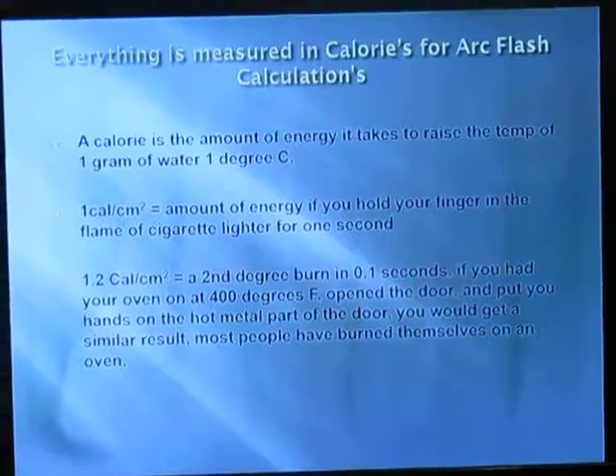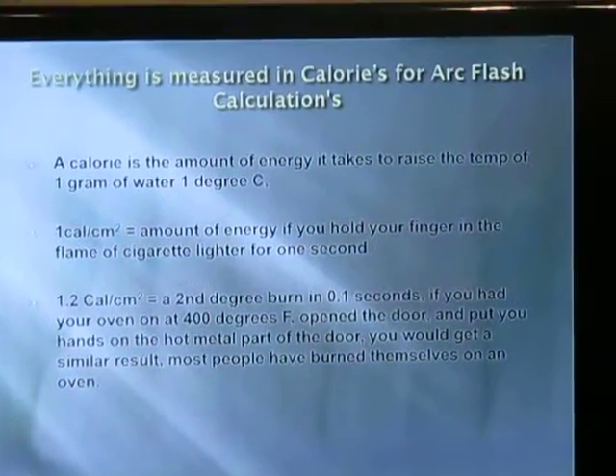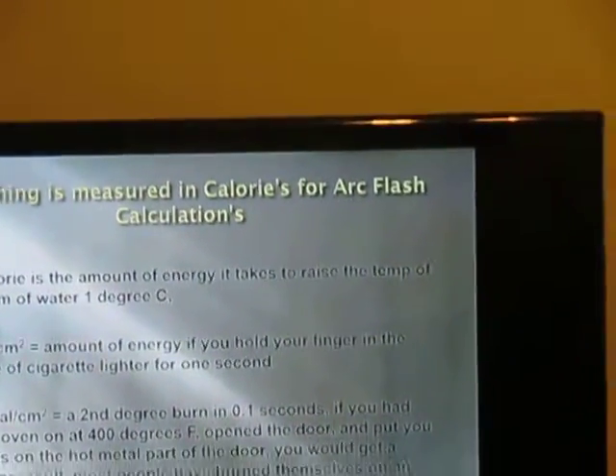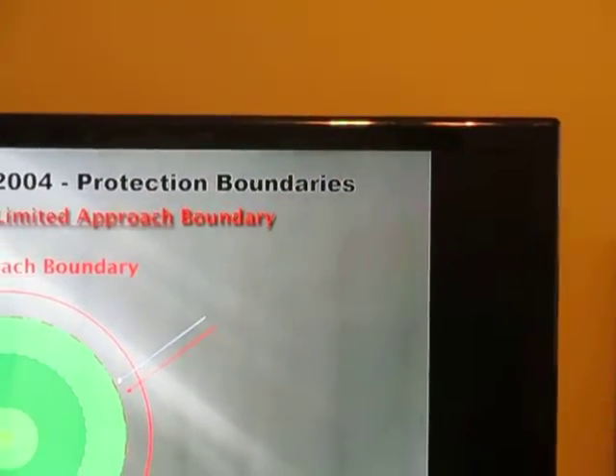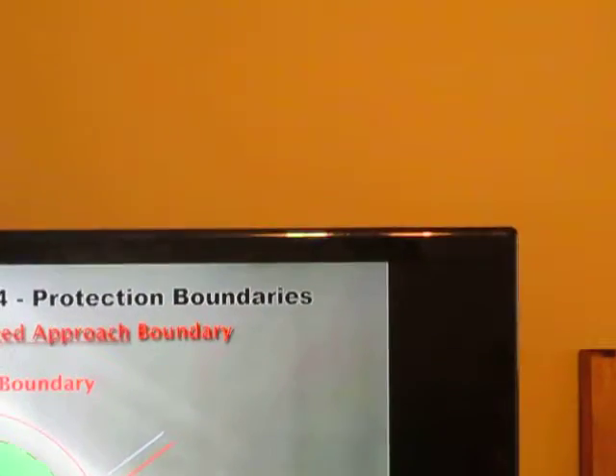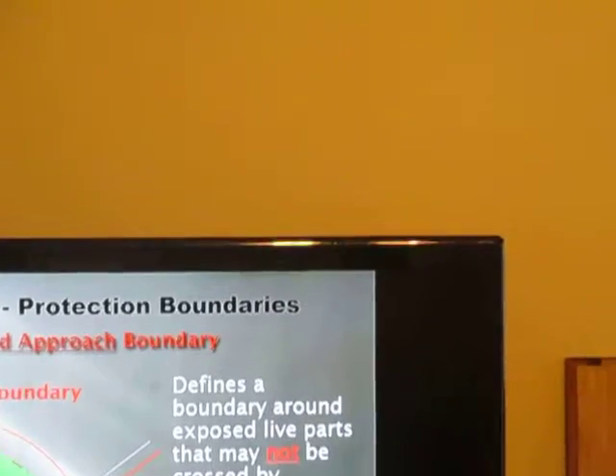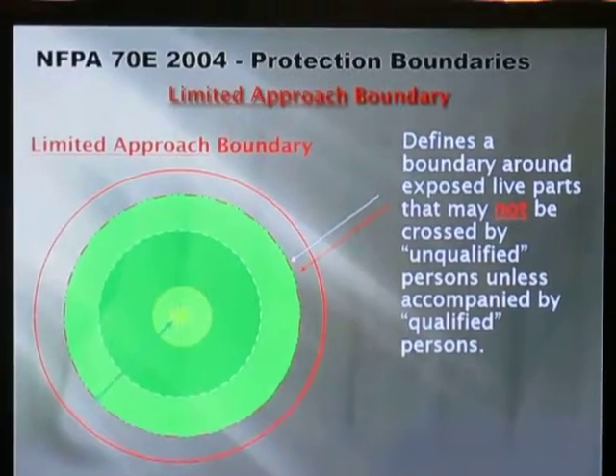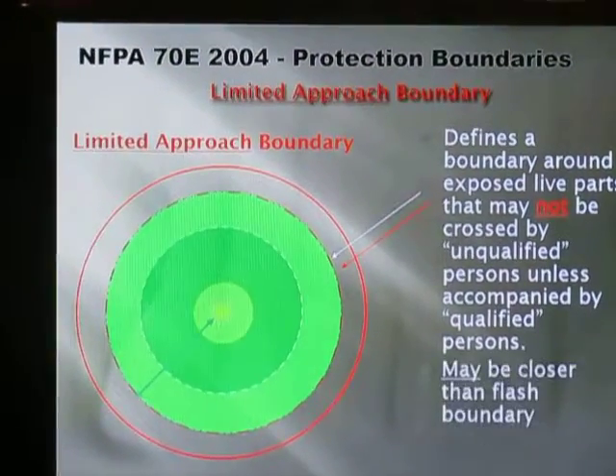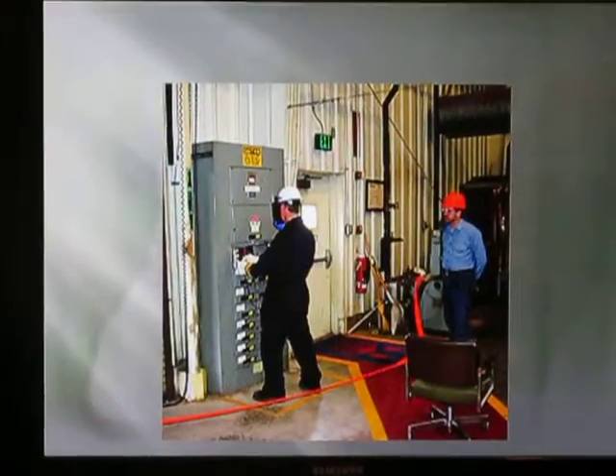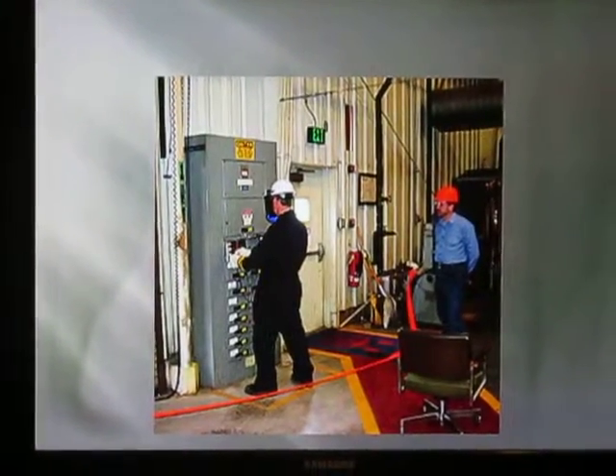And this is how they calculate the calories. A calorie is the amount of energy it takes to raise the temperature of 1 gram of water by 1 degree Celsius. 1 calorie per centimeter squared equals the amount if you hold your finger over a flame for 1 second. 1.2 calories per centimeter squared is a second-degree burn in 0.1 seconds, as if you put your hand on the oven door. And NFPA has these different boundaries they require. This is the limited approach. It defines a boundary around exposed live parts that may not be crossed by unqualified persons unless accompanied by a qualified person. Maybe closer than the arc flash boundary. That picture just shows an example of the boundary.